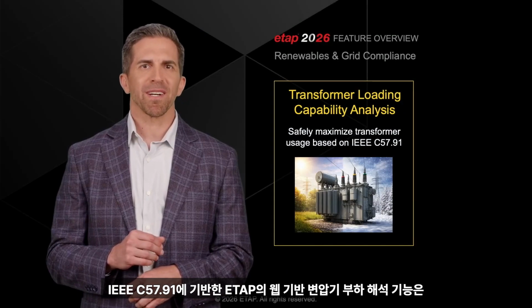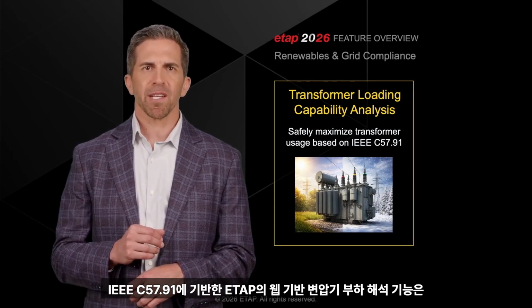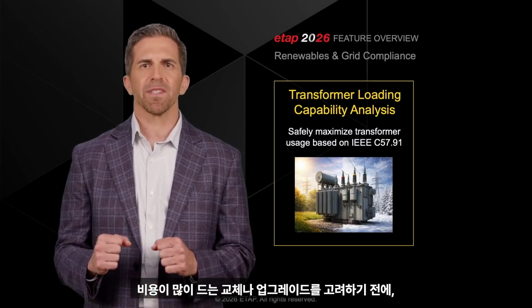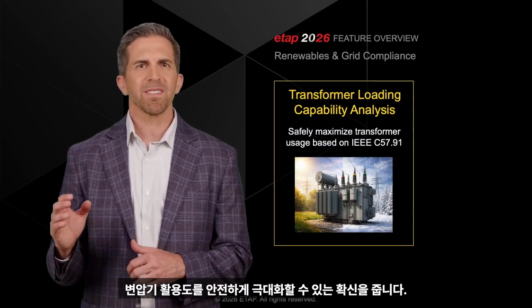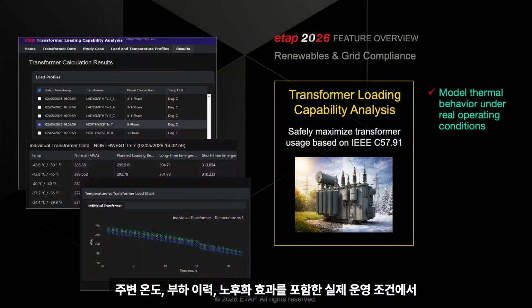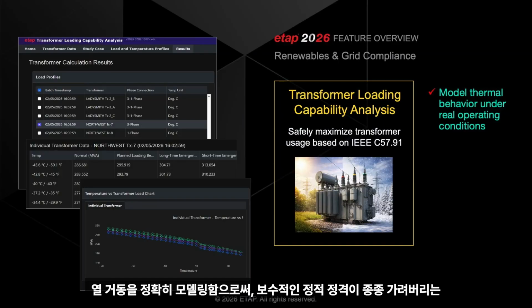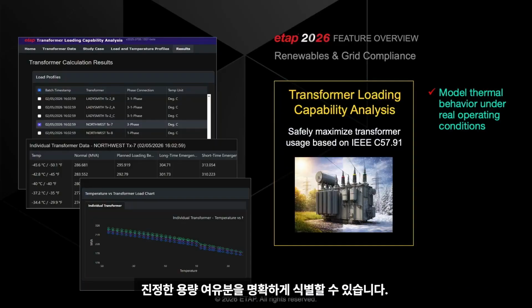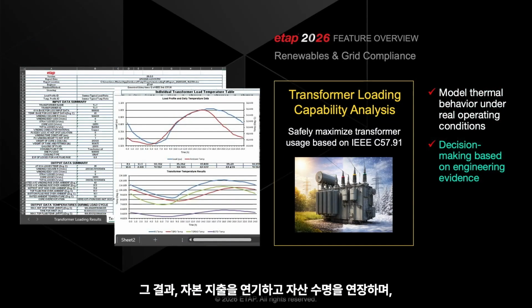ETAP's web-based transformer loading analysis capability, grounded in IEEE C57.91, gives transmission owners the engineering confidence to safely maximize transformer utilization before considering costly replacements or upgrades. By accurately modeling thermal behavior under real operating conditions, including ambient temperature, load history, and aging effects, operators can identify true capacity margins that conservative static ratings often obscure. The result is a data-driven foundation for deferring capital expenditures, extending asset life, and making replacement decisions based on engineering evidence rather than precaution. ETAP 2026 transforms grid operation from a constraint-driven challenge into a data-driven, engineering-led opportunity.